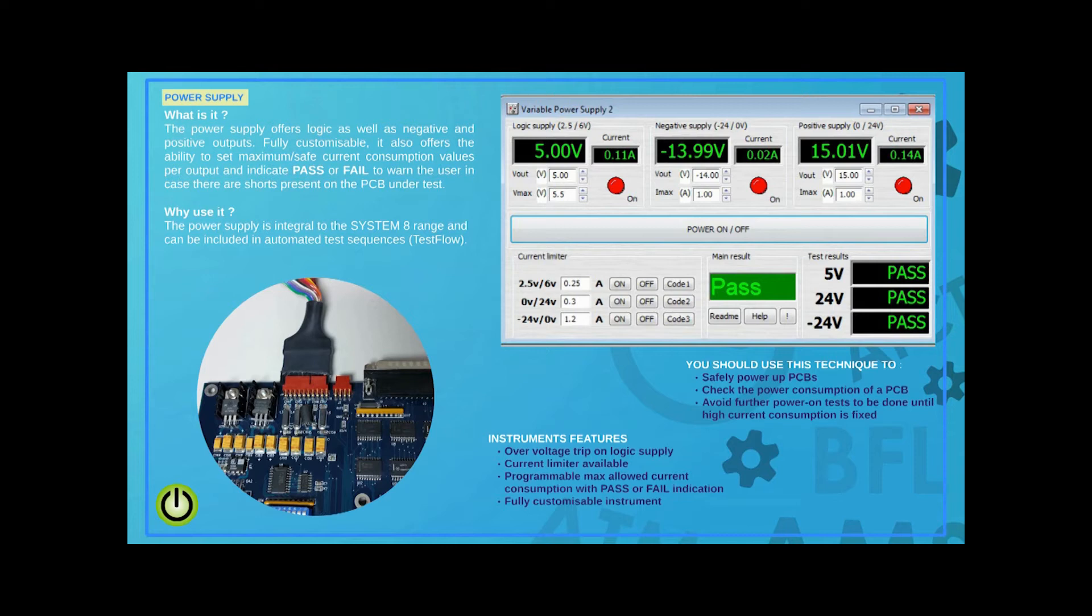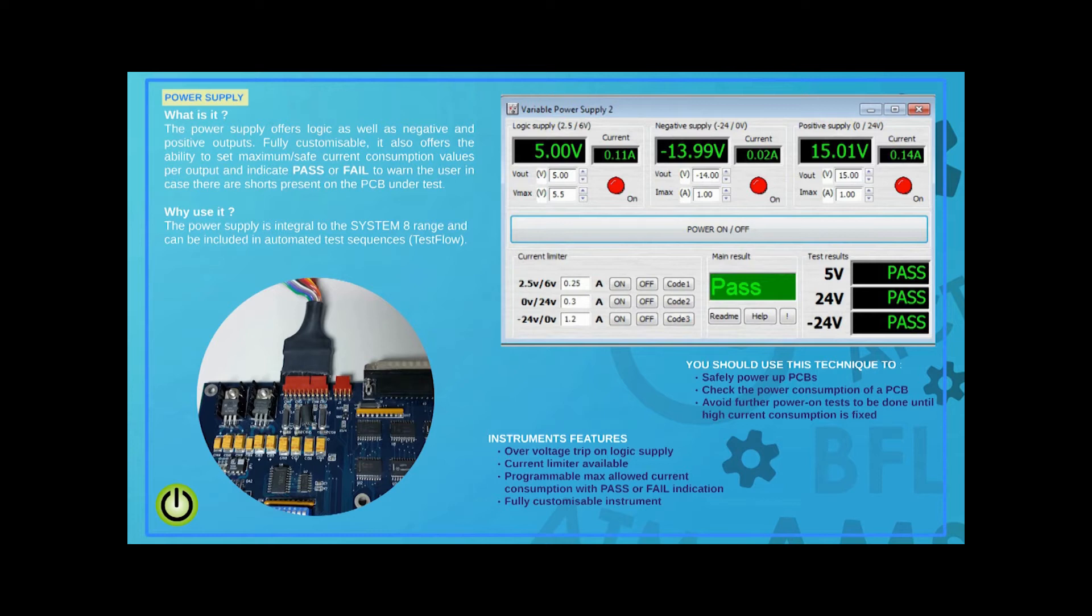System 8 features make applying power to a PCB safer and more effective. The built-in power supply is controlled by ABI's Ultimate software. The software can be configured to, for example, instantly stop testing if the amount of current being drawn by the PCB exceeds a predefined limit.